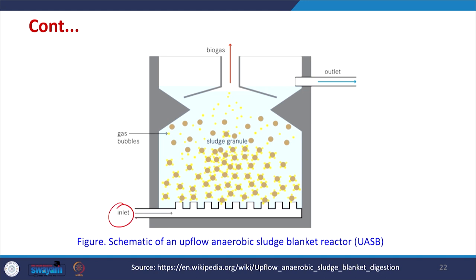In the UASB reactor, the inlet is at the bottom and wastewater flows upward through a sludge blanket containing anaerobic granules. Treatment happens as wastewater passes through the blanket. Gas formation also occurs and biogas — including methane — is taken out from the top. The treated wastewater exits from the side. You can refer to the UASB lecture for further detail on reactor operation.